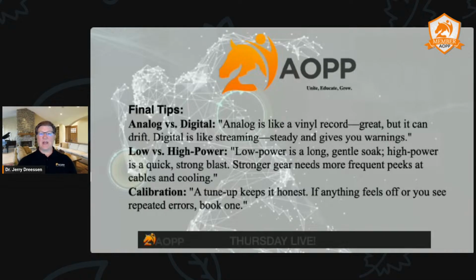And then final tips again: analog versus digital. Analog's like a vinyl record. It's great, but it can drift like a guitar getting out of tune. Digital's like streaming. It's steady and gives you warnings. Low versus high power. Low power is a long, gentle soak. High power is a quick, strong blast. And so stronger gear needs more frequent checks as far as when it peaks, and also cables and cooling. So some things to think about. And then calibration. The tune-up keeps it honest. If anything feels off or you see repeated errors, then definitely book a tune-up with your manufacturer.